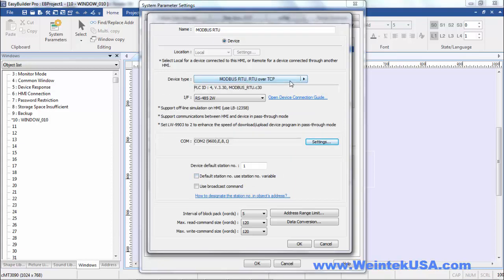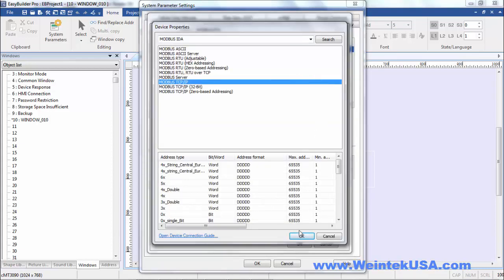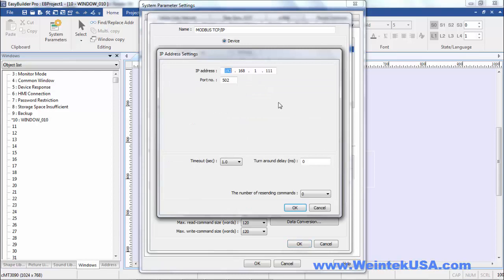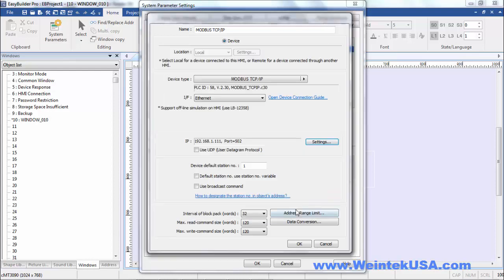Now if we had selected an Ethernet driver, of course we have Ethernet here selected now. And under the settings tab, we would have an area to set up our IP address. Now this is the IP address of the device that the HMI is talking to. The port is probably fine. Here again you can set a timeout and a turnaround delay and number of resending commands. If it's a protocol that requires a station number, you can define it here. Or you can dynamically define the station number in the register addressing and you can see how to do that down here.